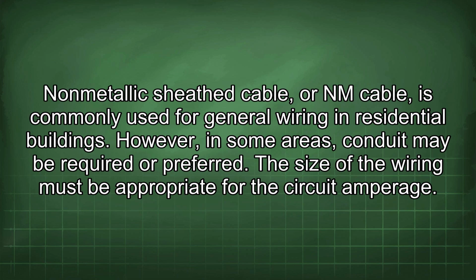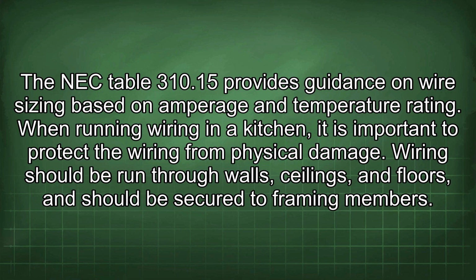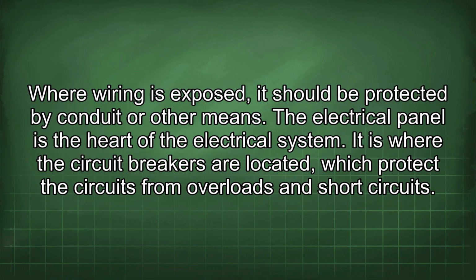Non-metallic sheathed cable, or NM cable, is commonly used for general wiring in residential buildings. However, in some areas, conduit may be required or preferred. The size of the wiring must be appropriate for the circuit amperage. The NEC Table 310.15 provides guidance on wire sizing based on amperage and temperature rating. When running wiring in a kitchen, it is important to protect the wiring from physical damage. Wiring should be run through walls, ceilings, and floors, and should be secured to framing members. Where wiring is exposed, it should be protected by conduit or other means.